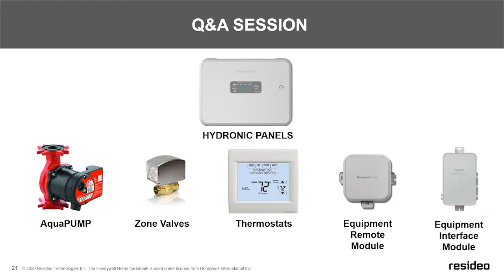Unfortunately, because we have a single source of where we're bringing in the hydraulic fluid and dispersing it over those 2 rooms, we can't really split that into 2 zones. However, with the T10 and the sensors, we can do some averaging. And so that is going to allow us to look at the loads in those 2 rooms and be able to kind of equalize what's available and where they sit at. But it's not true zoning at that point, but it is at least closer to the comfort probably that we're looking for.